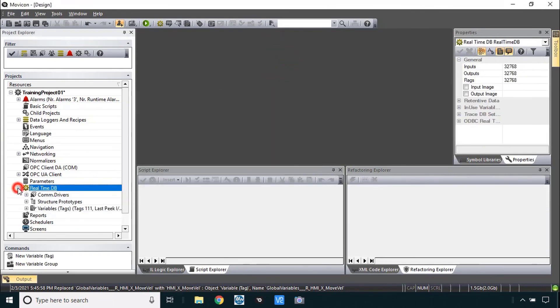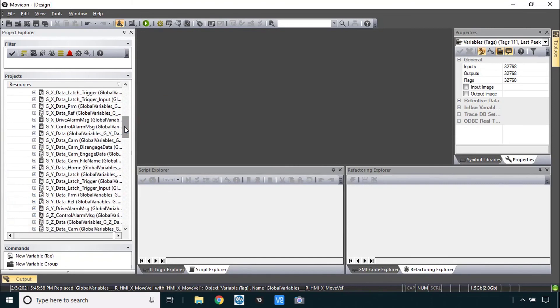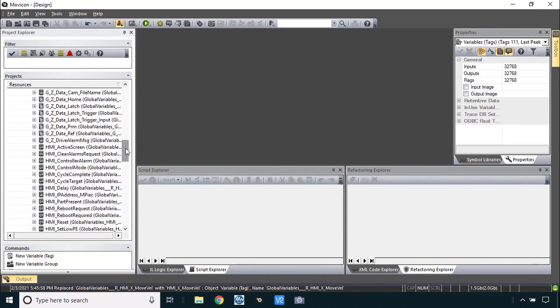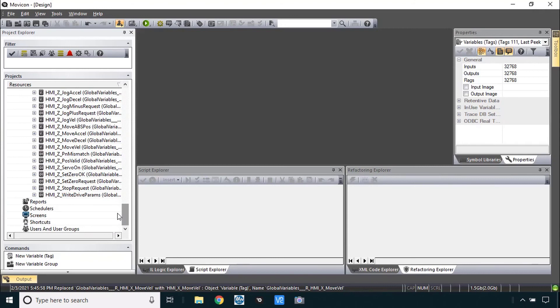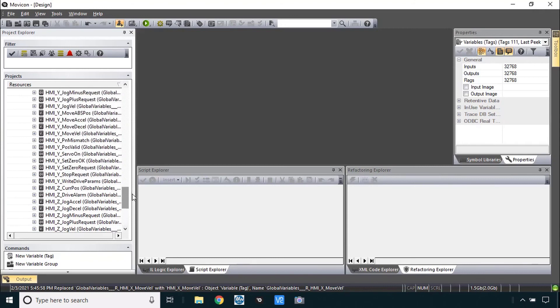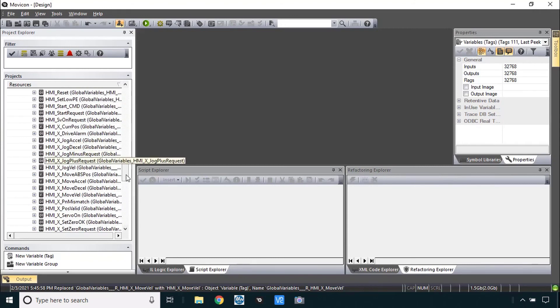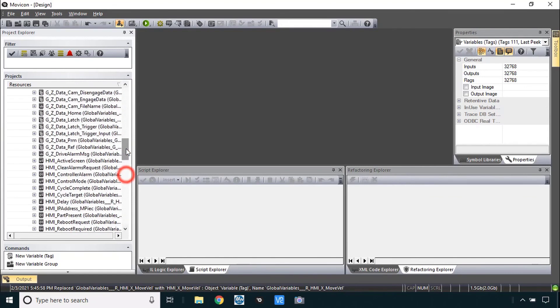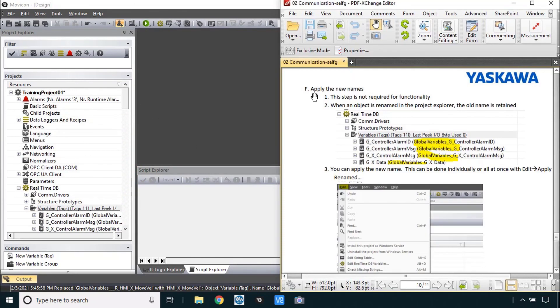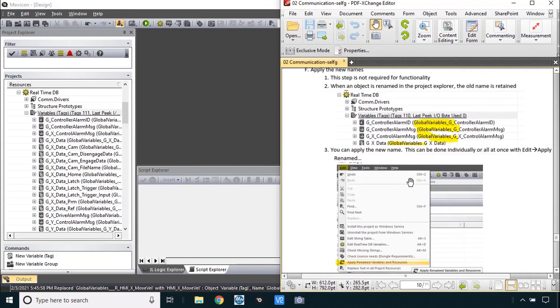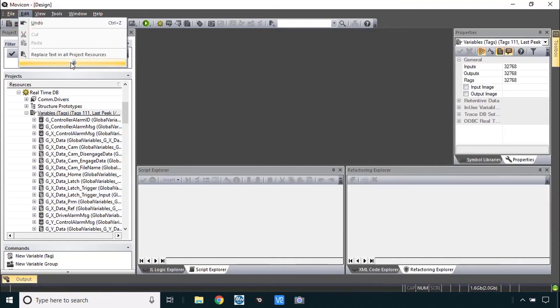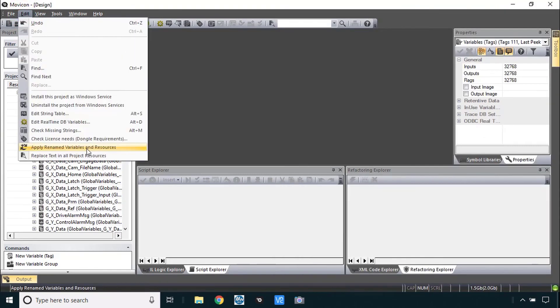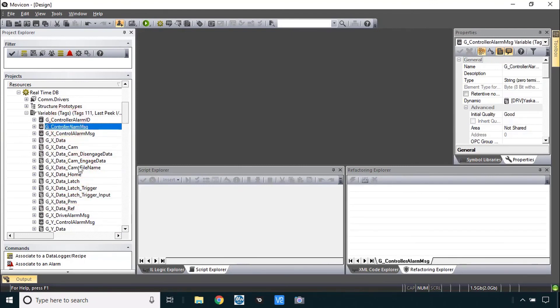I'll close this and just take a look at your real time DB with your variables. And they should all start with either G underscore or HMI underscore. And that will just make them a lot easier to work with. So you can recognize the distinguishing part of the name as you're configuring the HMI buttons. The last step here says to apply the new names which is not required for functionality. What's going on here is you see the old name is preserved and that's fine. But you can apply a new name here under the edit menu. Apply renamed variables. Edit. Apply renamed variables and resources. And now when you click on here it'll refresh. And you'll just see the simple name that is currently in use. So that's the end of this mini lab.